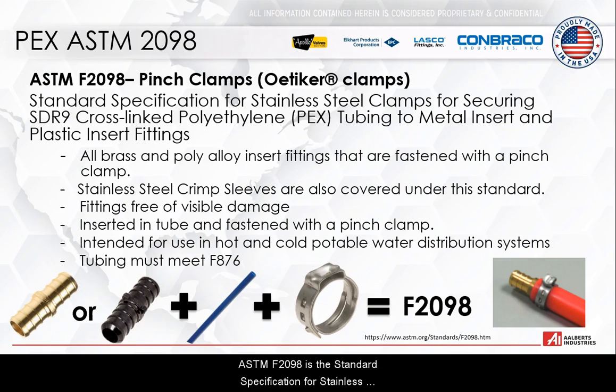ASTM F2098 is the standard specification for stainless steel clamps for securing PEX tubing to metal insert and plastic insert fittings. Pinch clamps are also known as Oetiker clamps. The conceptual formula at the bottom shows you can fasten either brass or polyalloy fittings with a pinch clamp. The standard also covers the stainless steel crimp sleeves.